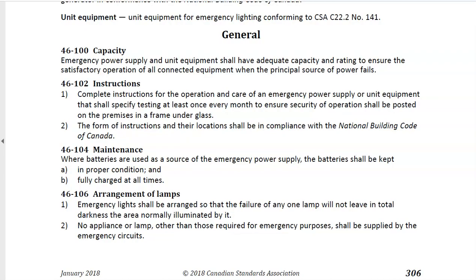Take a look at Section 46. 46.102 over here talks about instructions. Complete instructions for the operation and care of emergency power supply equipment or unit equipment, which shall specify testing at least once a month to ensure security of operation, shall be posted on the premises in a frame under glass. This is Section 46, which we'll cover more later this week, but that deals with emergency lighting supply systems.